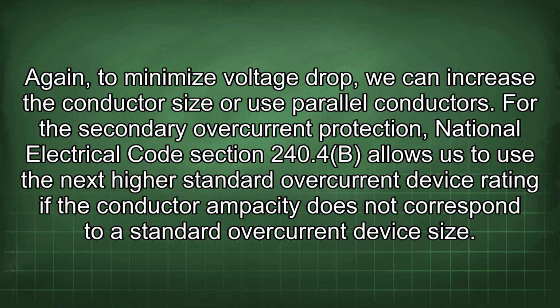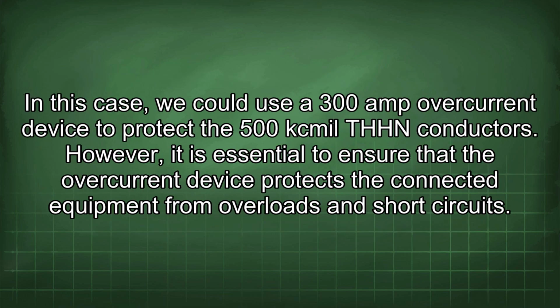For the secondary overcurrent protection, National Electrical Code Section 240.4(B) allows us to use the next highest standard overcurrent device rating if the conductor ampacity does not correspond to a standard overcurrent device size. In this case, we could use a 300 amp overcurrent device to protect the 500 kcmil-THHN conductors. However, it is essential to ensure that the overcurrent device protects the connected equipment from overloads and short circuits.